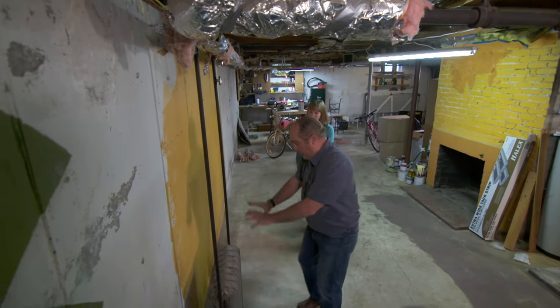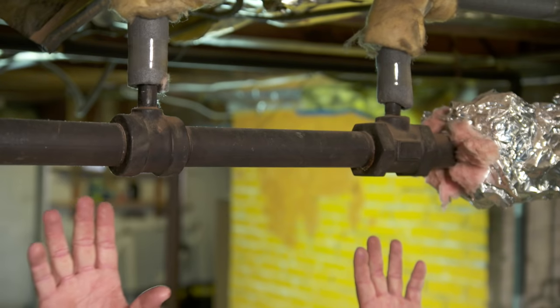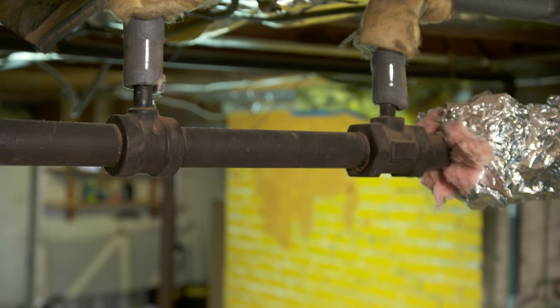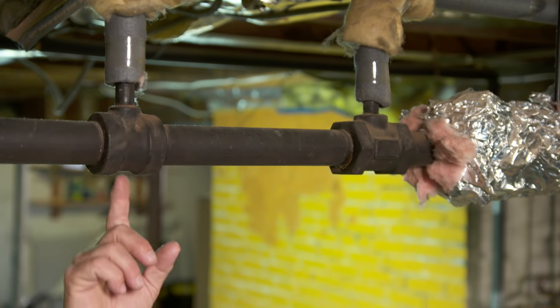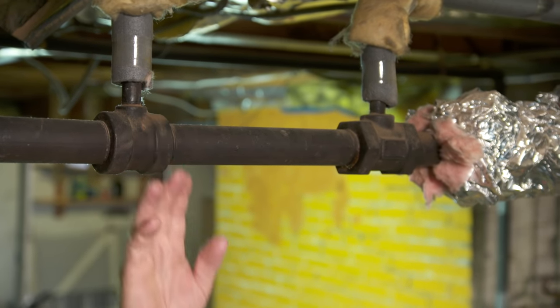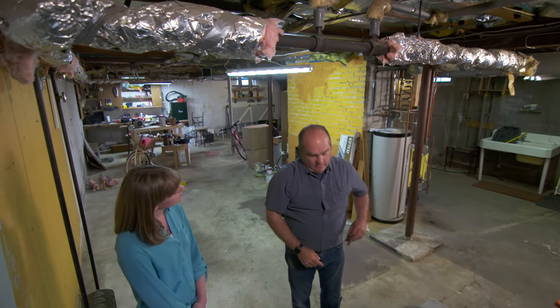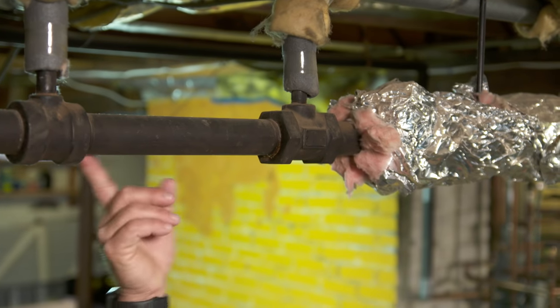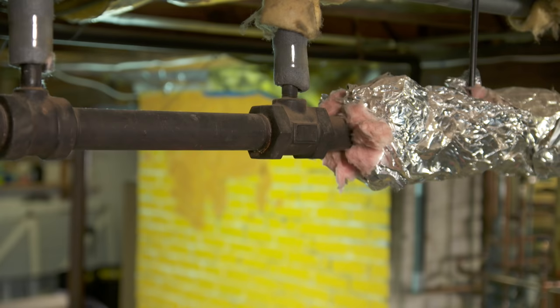You have a set of T's going to each single radiator — here's one that goes up to the radiator that's not working. Here's the highway; the water moves through this trunk with two T's here. Why would the water ever want to go up through those T's and take the off-ramp through the radiator? An engineer back in the 50s invented a simple solution: this T is a little different — it's called a diverter T, or a monoflow T.